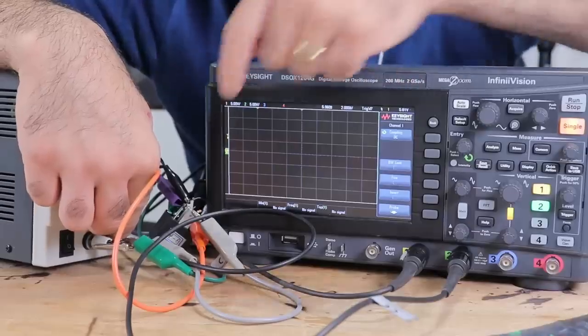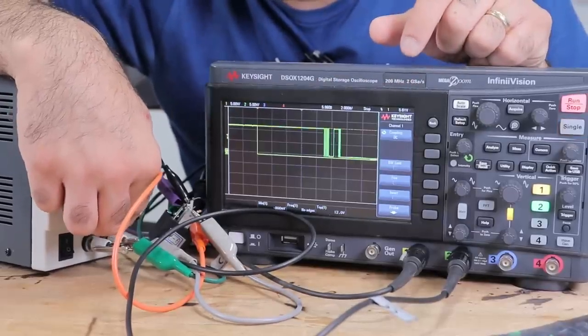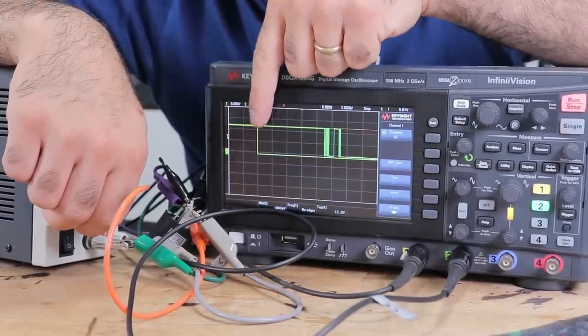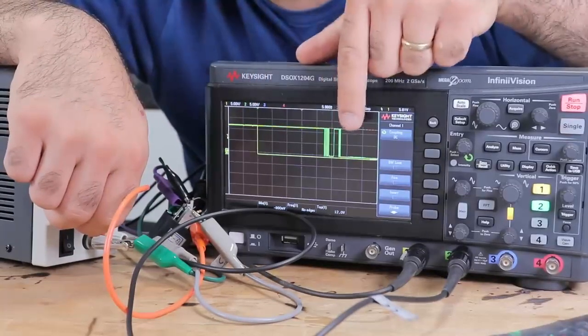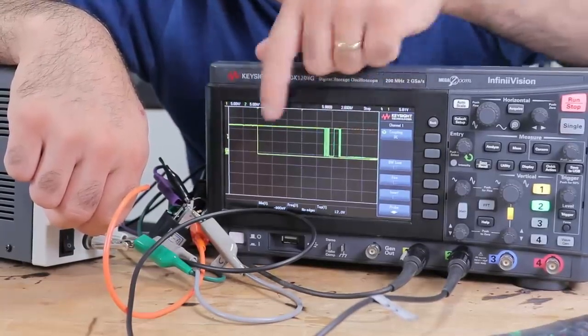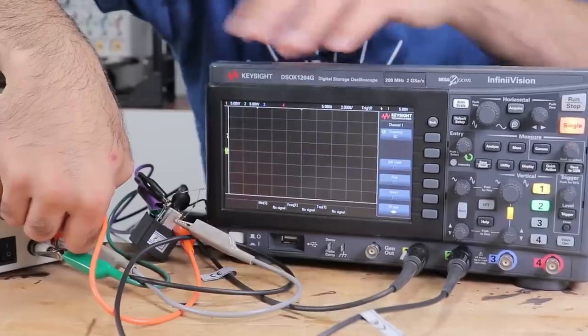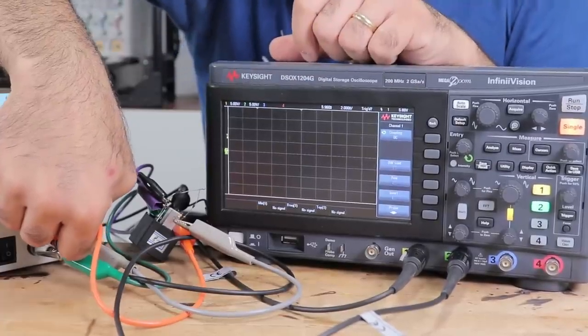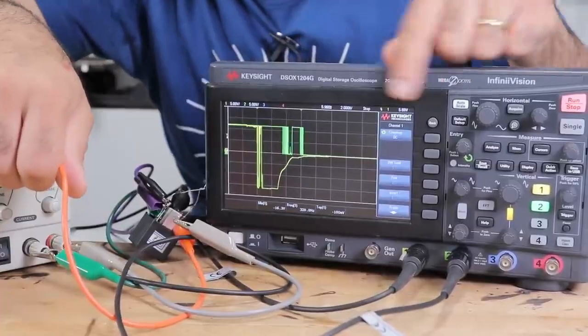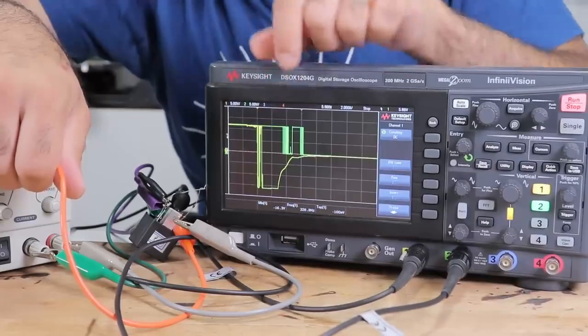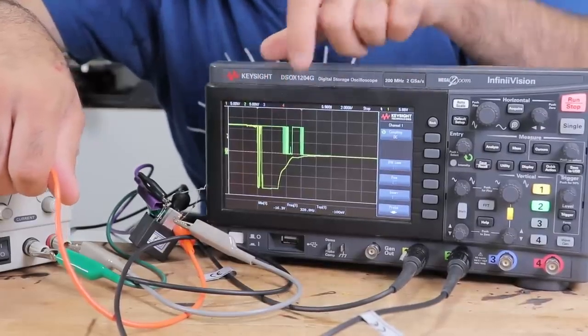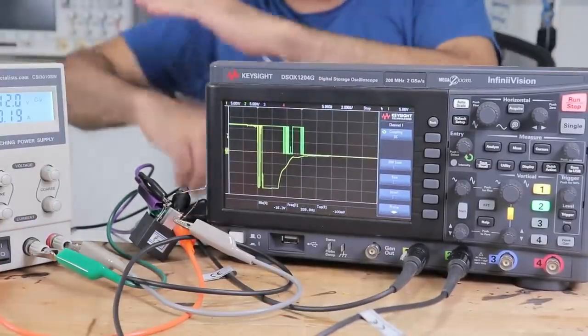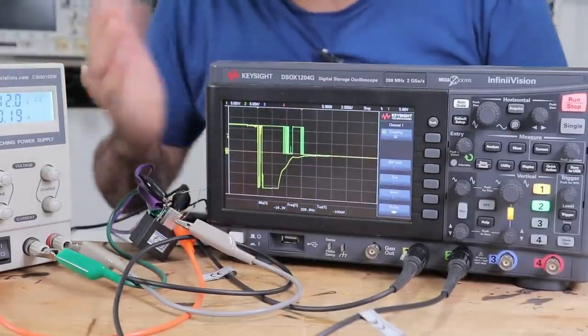Here's a test with a single flyback diode. There, from the yellow line where the coil turns off to when the switch switches, it takes around 10 milliseconds. And here's the test with an addition of a 15-volt Zener. See? Now it takes less than 4 milliseconds to switch. The pulses you see on the relay switch are because of the relay contacts bouncing against each other when they switch. Fun!